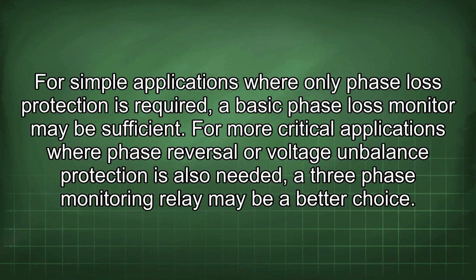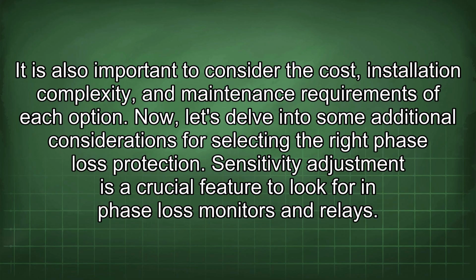For simple applications where only phase loss protection is required, a basic phase loss monitor may be sufficient. For more critical applications where phase reversal or voltage imbalance protection is also needed, a three-phase monitoring relay may be a better choice. It is also important to consider the cost, installation complexity, and maintenance requirements of each option. Now, let's delve into some additional considerations for selecting the right phase loss protection.